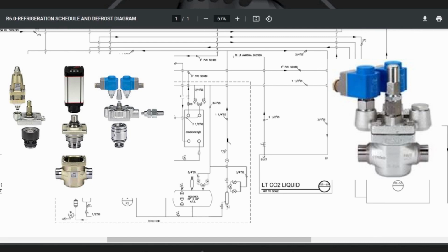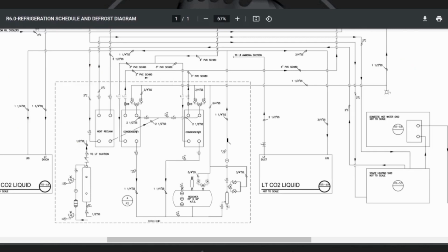Any reason why? No, that was a choice of Zero Zone. Oh, okay. But we're happy with Danfoss. They work fine. We haven't had any issues with them. And the system on the ammonia side holds approximately how much ammonia refrigerant? There's 135 pounds of liquid ammonia, 3,000 pounds of CO2 in the medium temp, and about 1,000 pounds of CO2 in the low temp. Wow. But you're also doing all your chillers and everything else, right? Yeah, it's everything in the store, all the mechanical equipment.